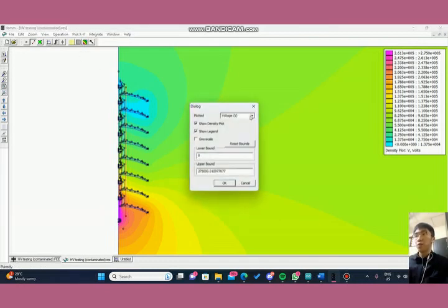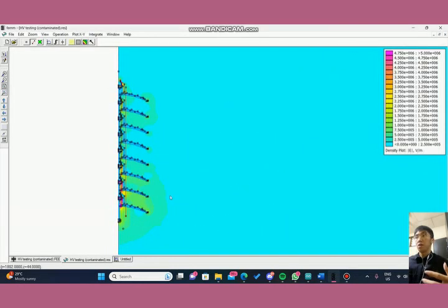For the next one, the plot of the field density, which we are more concerned about, this is the density plot color graph. As we compare to the dry conditions, we can see that the distribution of the E field becomes more uneven due to the accumulation of dust, and it becomes more severe at the bottom, near the insulator. This is because the field intensity that is supposedly distributed evenly throughout the insulator becomes uneven, and a smaller area in exchange gets higher field intensity at certain points.